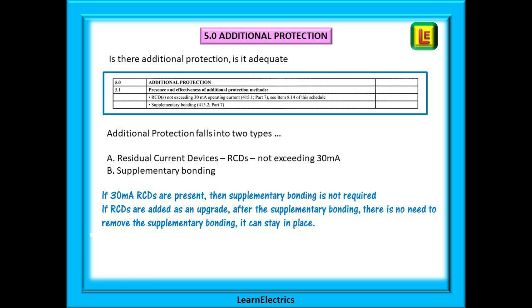Section 5 looks at additional protection. Additional protection is protection in addition to the fuses or breakers. There are two types recognised by the wiring regulations: protection by 30 milliamp RCD, and supplementary bonding of all exposed and extraneous metalwork in a location. Supplementary bonding and main bonding are two different things — don't get them confused. If 30 milliamp RCDs are present, supplementary bonding is not required. However, if RCDs are added as an upgrade to an installation that already has supplementary bonding, there is no need to remove it — it can stay in place.